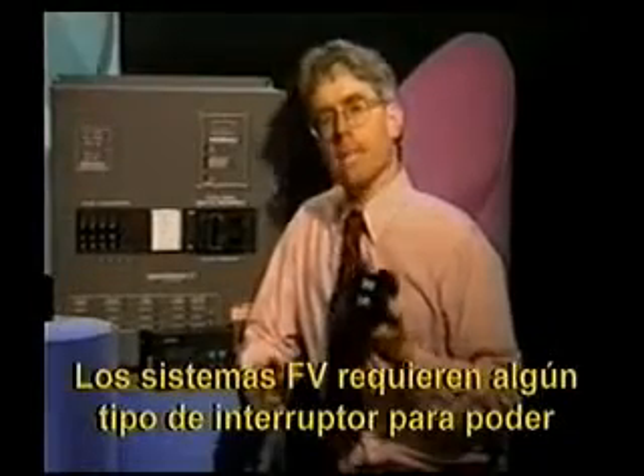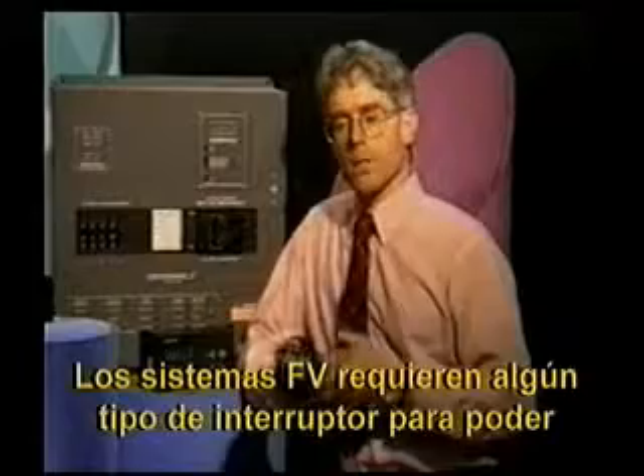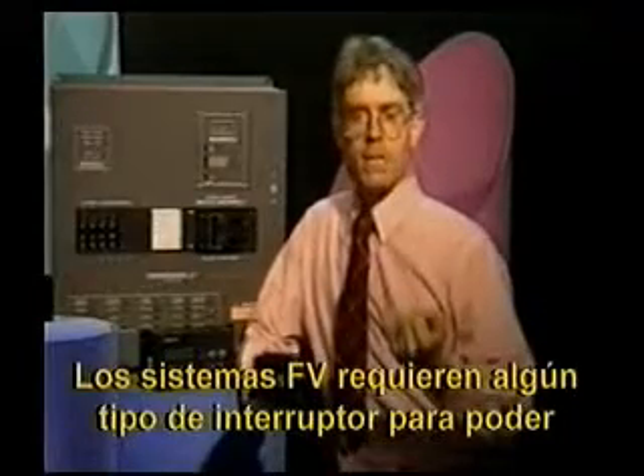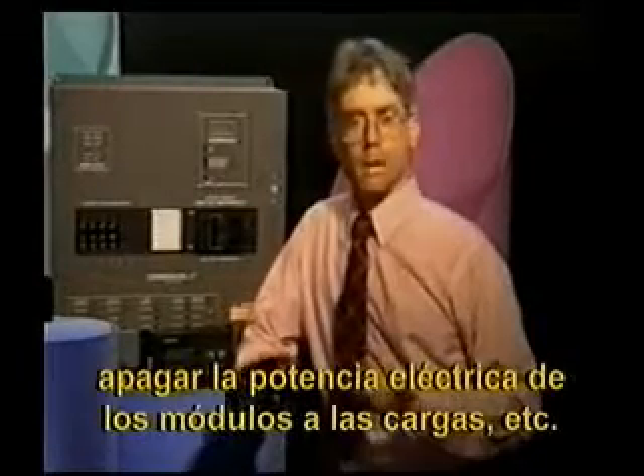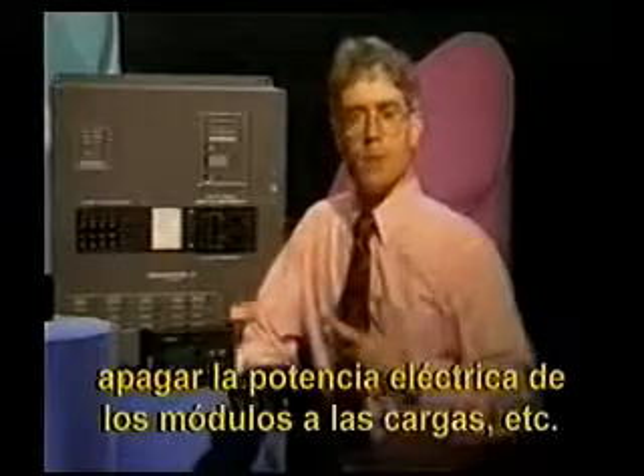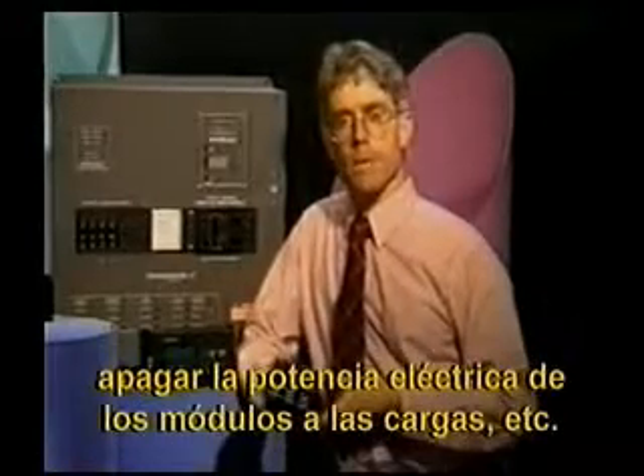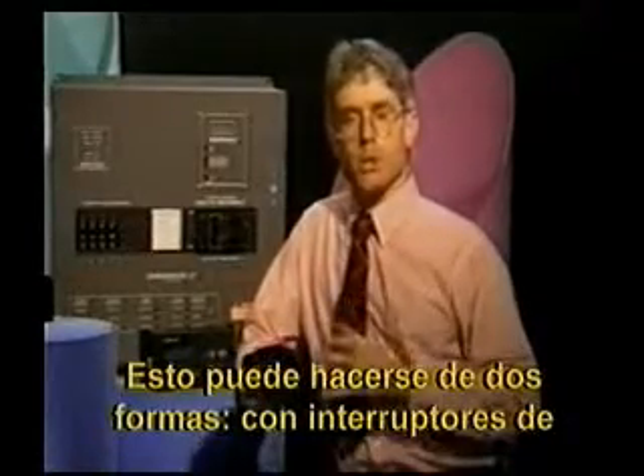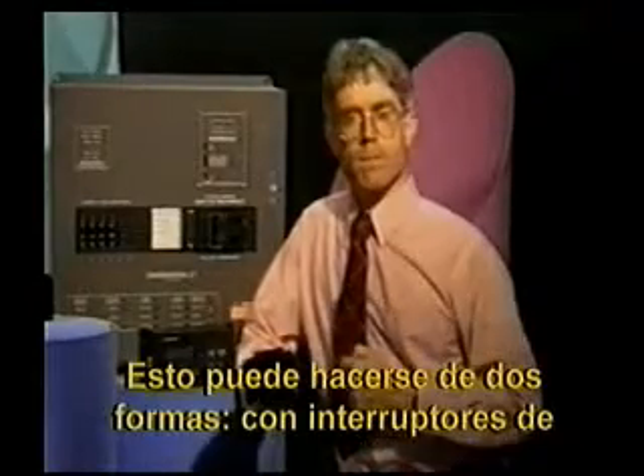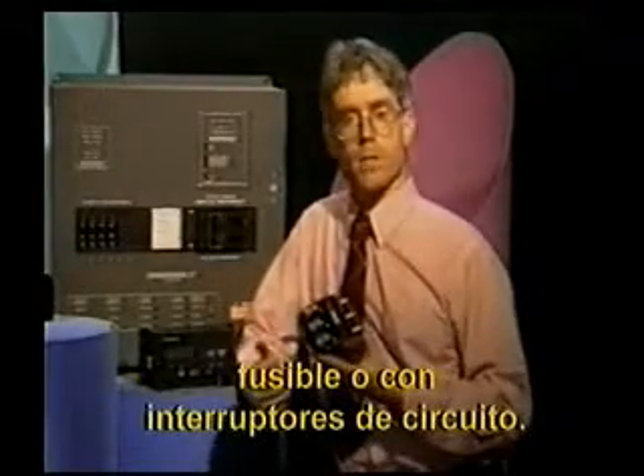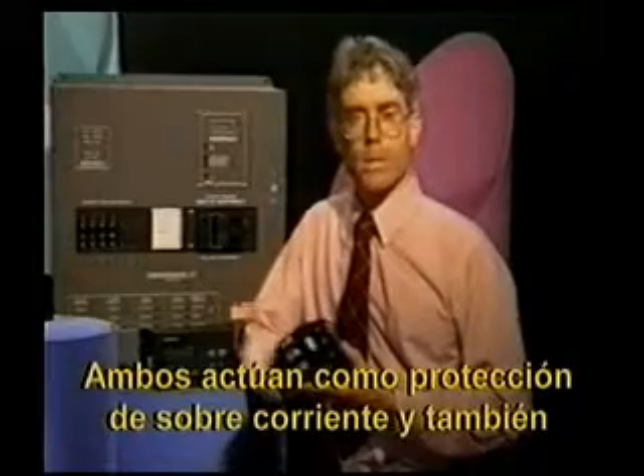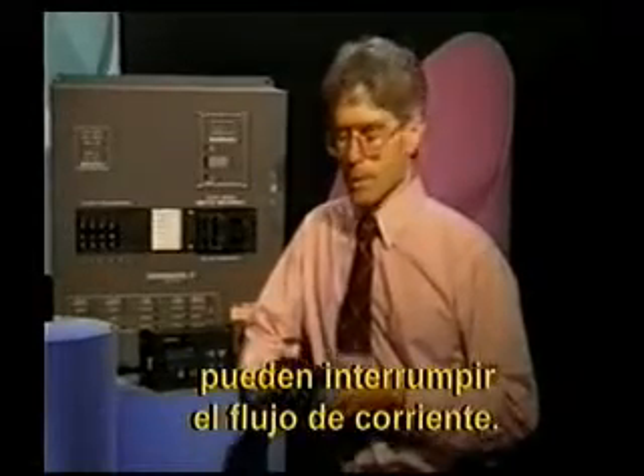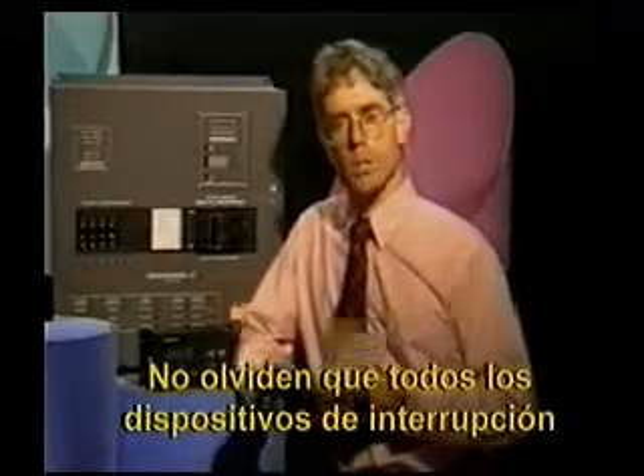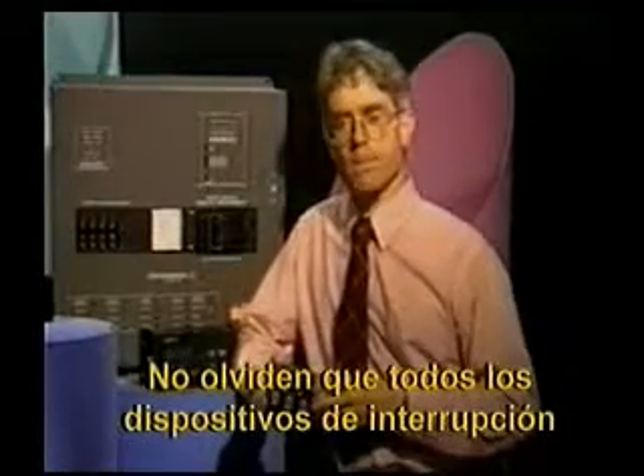In all of our photovoltaic systems, we're going to want to install some sort of switching so that we can turn off our electrical power, both from our modules and to our loads and so on. This can be done in two ways. We can either use fused switches, or we could actually use circuit breakers. They both act as overcurrent protection and also can break the current flow. So we can use circuit breakers or fused switches in these various locations in our system.